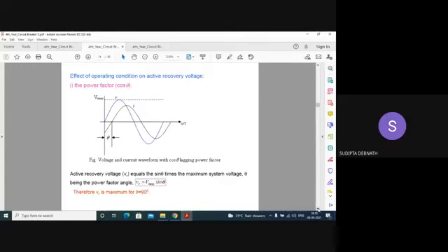Now, it depends upon some phenomena. See, the active recovery voltage Vr equals Vmax sin theta. Okay. Vr is maximum when theta equals 90 degrees, because the value of active recovery voltage depends upon the power factor of the circuit. Okay. This is the power factor. It depends upon the power factor of the circuit.